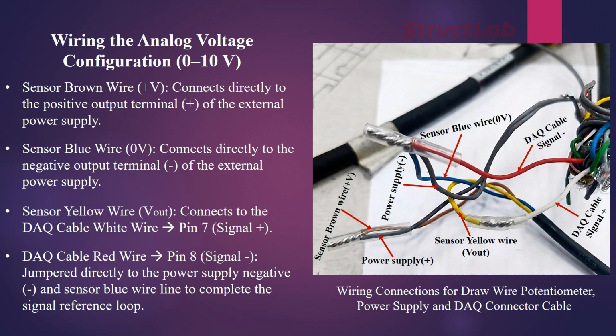Step 4. Wiring the analog voltage configuration. Make the wiring connections as shown in the diagram on the right. First, connect the sensor's brown wire to the positive terminal of the external power supply, and the blue wire to the negative terminal. Next, route the sensor's yellow output wire to the DAQ cable's white wire, which maps to pin 7 as signal plus. Finally, take the DAQ cable's red wire, which maps to pin 8 as signal minus, and jumper it directly to both the power supply negative and the sensor's blue wire, to complete the signal reference loop.